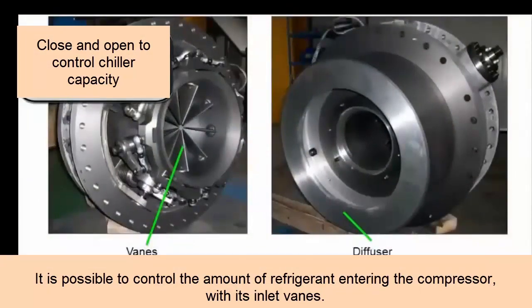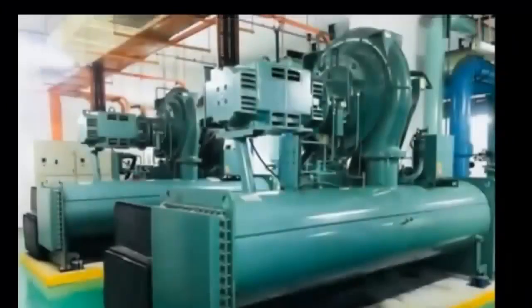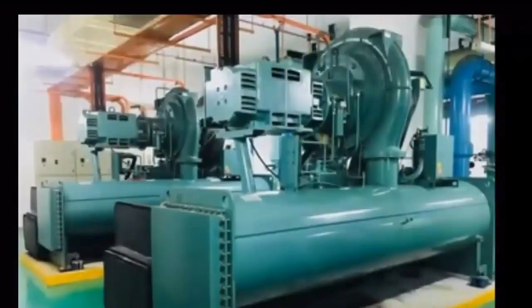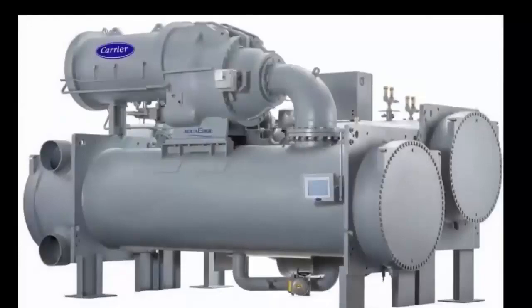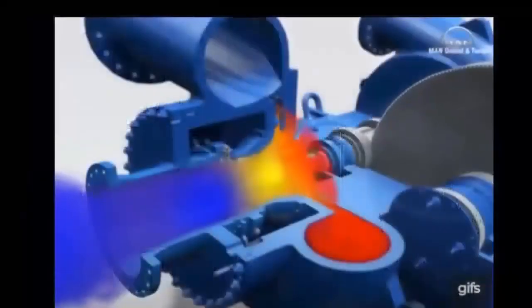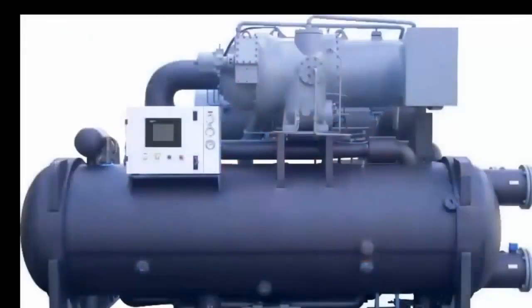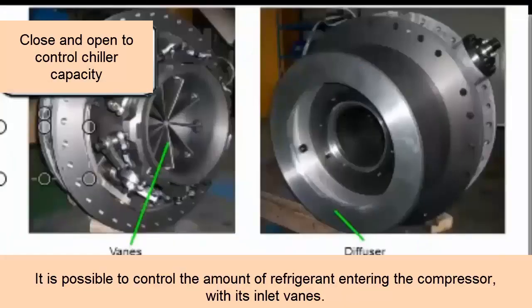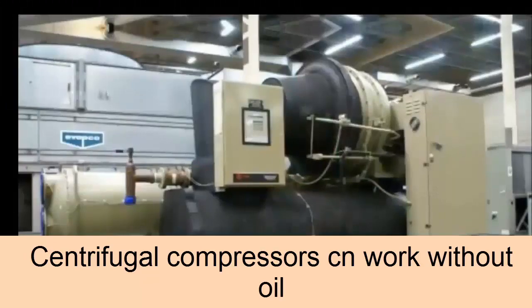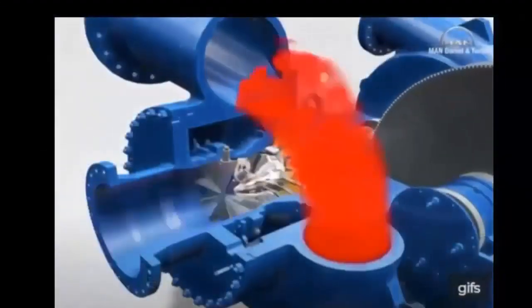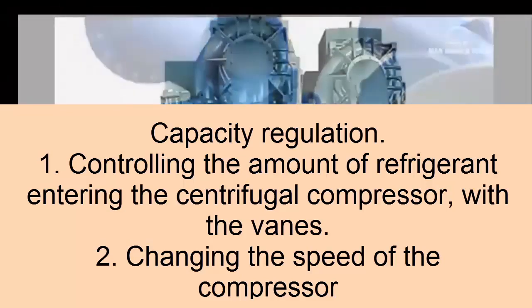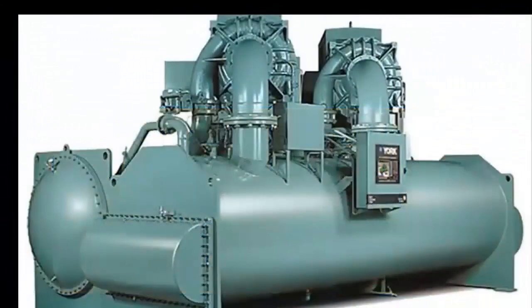As in all previous cases, we need to talk about capacity regulation. Whenever we talk about the chiller we discuss capacity regulation because it is the part that will allow us to adjust the electrical consumption to the cold production. The chiller with a centrifugal compressor will use two strategies to adapt to partial load. It uses the regulation of the refrigerant flow that enters the compressor through inlet vanes that can close and open to let more or less coolant through. The second regulation tip would be to vary the speed of the compressor. With these two parameters we will be able to adapt to the partial load, changing the input area to the compressor and varying the speed.